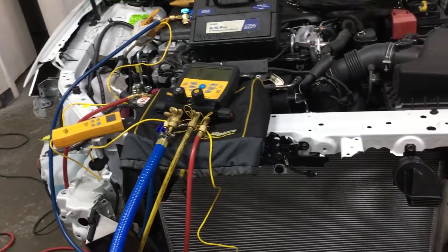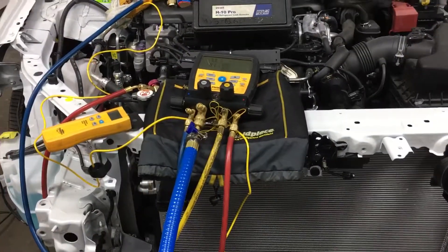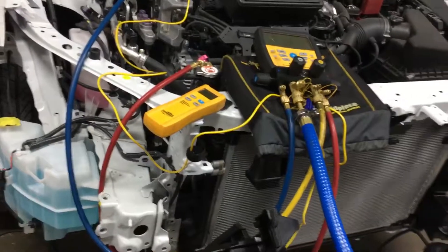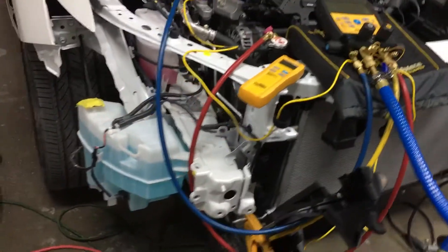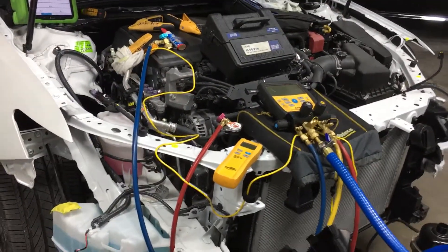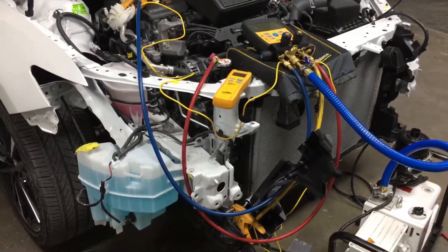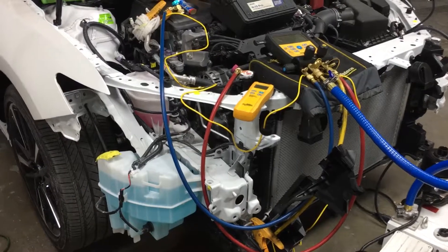It's very important on electric compressors not to expose them to the atmosphere, because you will not be removing all the moisture using a vacuum pump — especially in short time periods — and with little cheap vacuum pumps or the big recovery machine through manifolds.